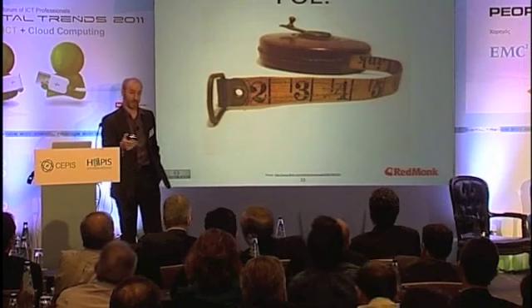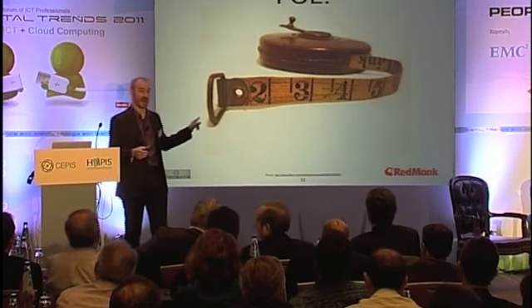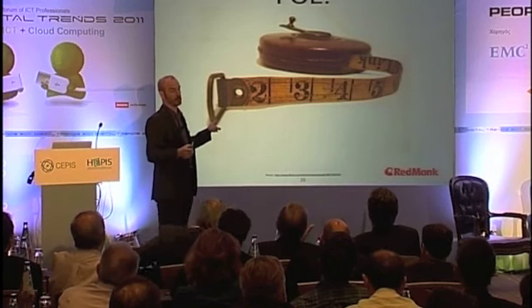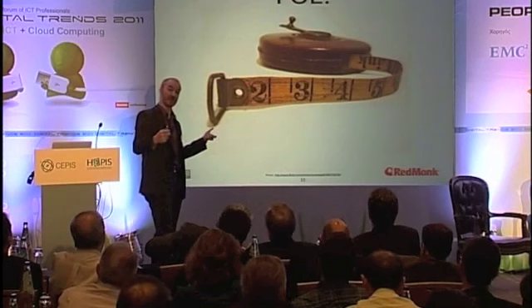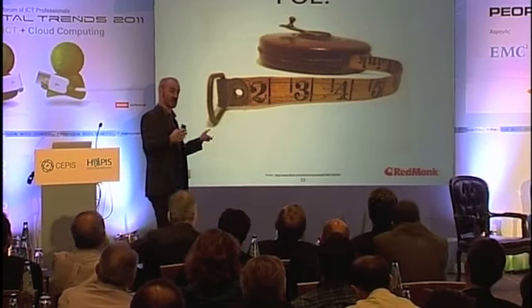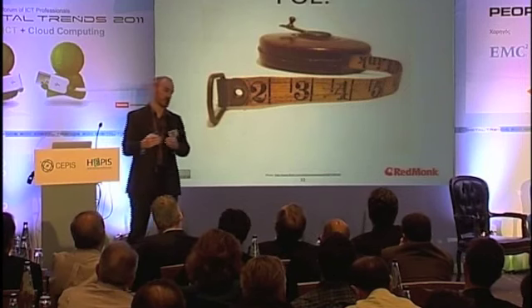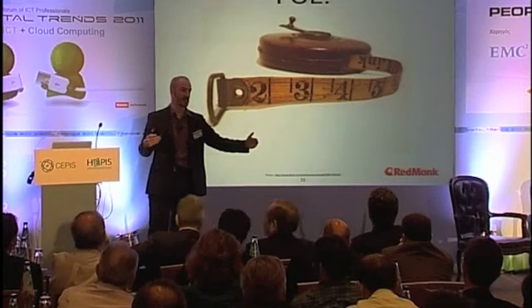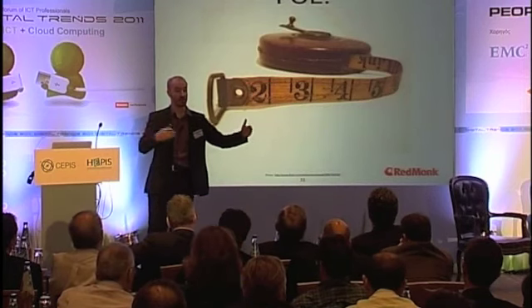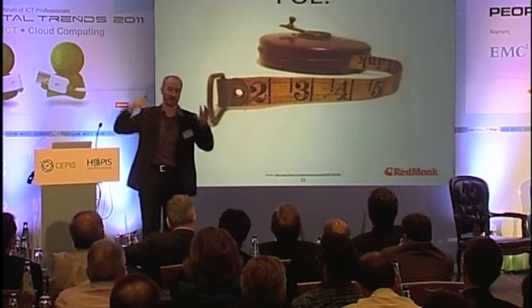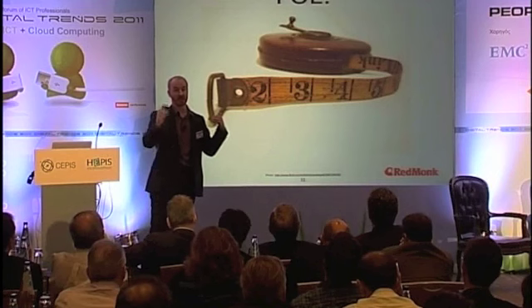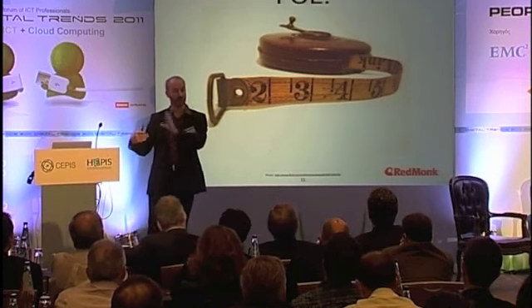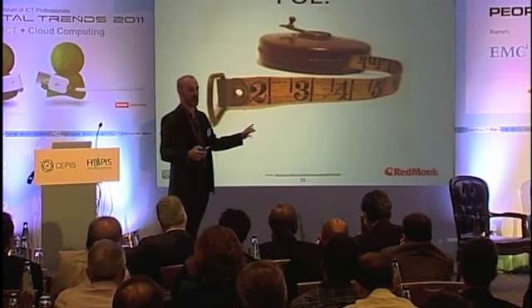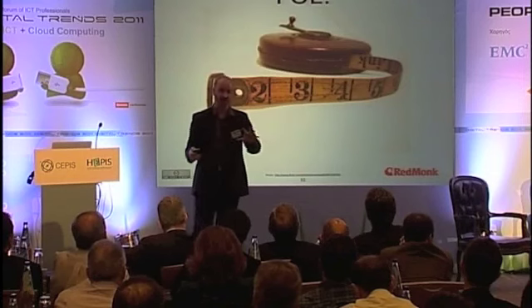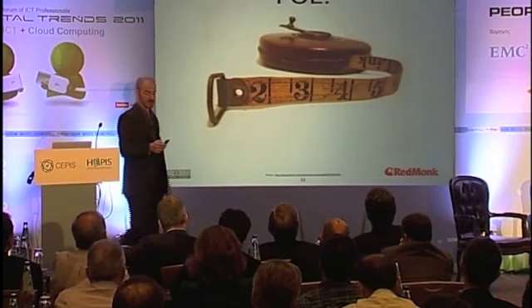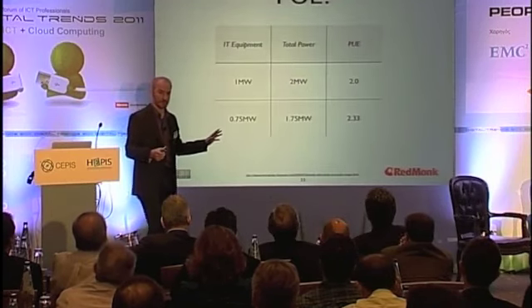Now, a couple of problems with PUE as a metric. The first is there hasn't traditionally been any standard about where you measure the power. It's measured at the electricity company power meter, but in data centers, that has often been measured on the high voltage side, the medium voltage side, or the low voltage side, depending on where they put the meter. And if one data center measured it at one place and another at another place, you can't cross-compare because you're leaving out the losses that occur in the conversion from high to medium to low voltage. So right there is the lack of standardization. That's being worked on at the moment, and it is getting better. They are starting to standardize, but traditionally it hasn't been standardized. So that's one issue straight away.